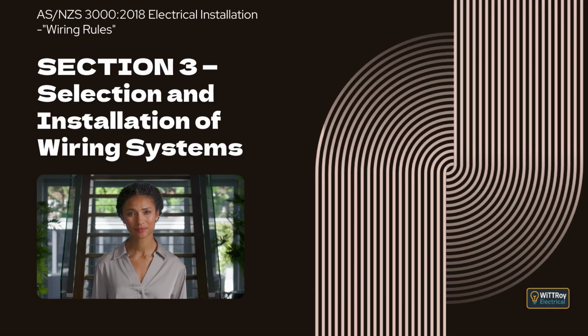Clause 3.11.4, Installation requirements. This clause explains that underground wiring systems must be installed in accordance with the detailed installation requirements that follow, and that the dimensions and arrangements shown apply in any direction where cover is relied upon to reduce the risk of damage during excavation. Clause 3.11.4.1, General. This clause states that underground wiring systems must be installed in accordance with the requirements that follow in this section, and that these requirements are intended to reduce the risk of damage and improve safety over the life of the installation.